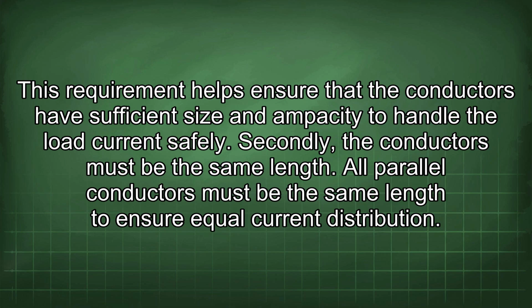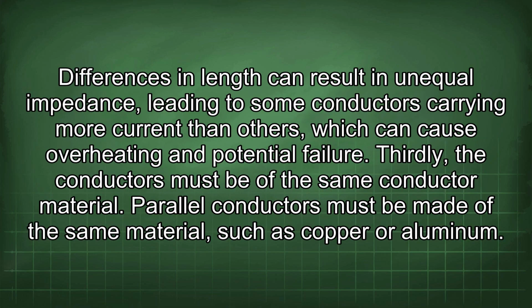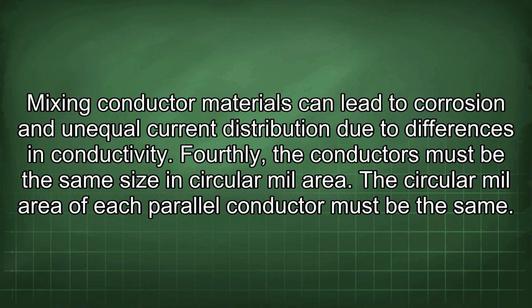Secondly, the conductors must be the same length. All parallel conductors must be the same length to ensure equal current distribution. Differences in length can result in unequal impedance, leading to some conductors carrying more current than others, which can cause overheating and potential failure. Thirdly, the conductors must be of the same conductor material. Parallel conductors must be made of the same material, such as copper or aluminum. Mixing conductor materials can lead to corrosion and unequal current distribution due to differences in conductivity.